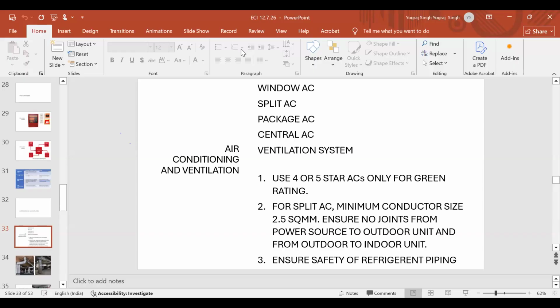Now, there's a split AC. You think of a split AC, where the split unit is provided in the balcony, and inside, your evaporator is there, where the fan is there, and the room is being cooled. Now, it is important to know that supply is coming from a distribution board, DB. DB may be close to your indoor unit, but first the supply will go from DB to the outside unit. From the outside unit, one wire without any joints will come to your indoor unit. What will happen?